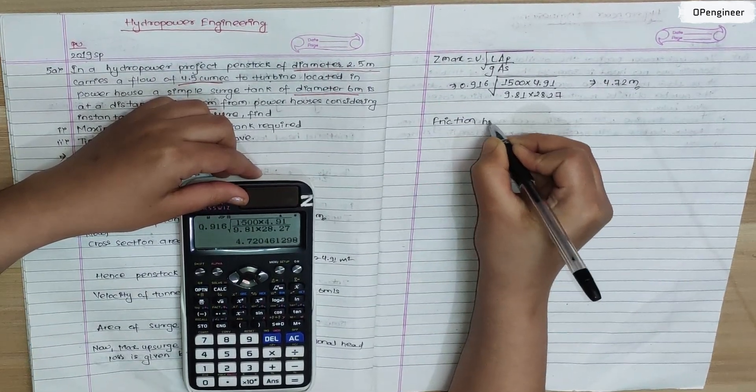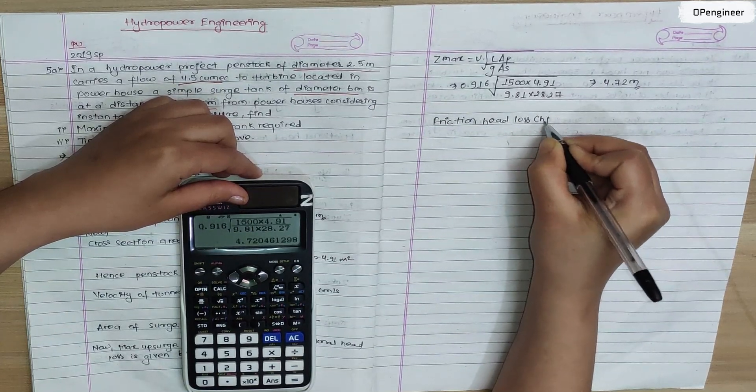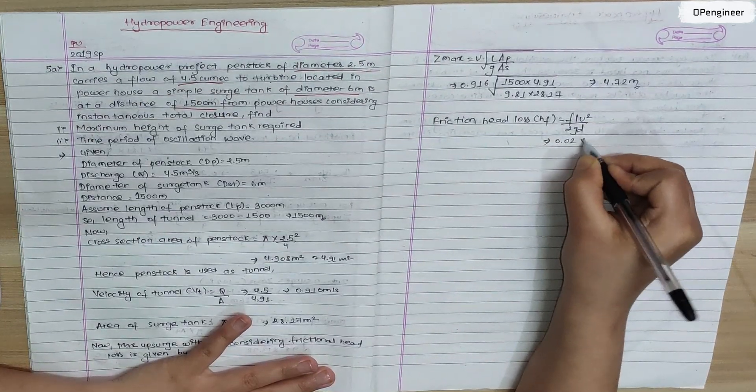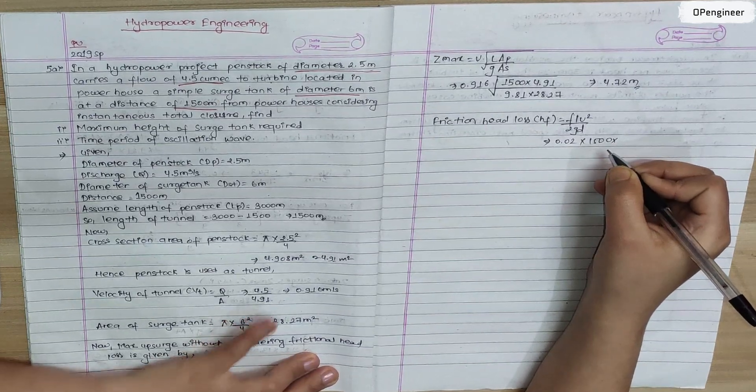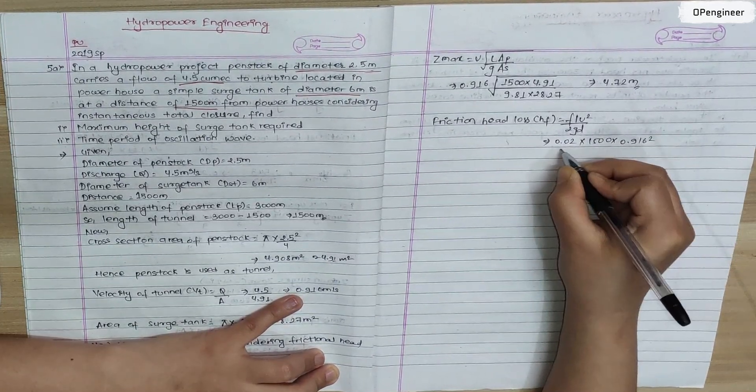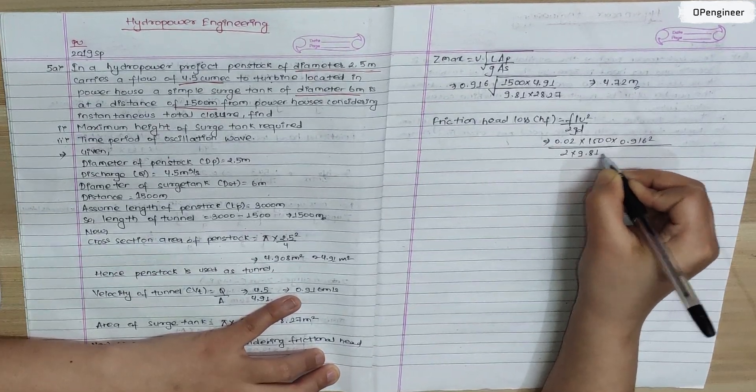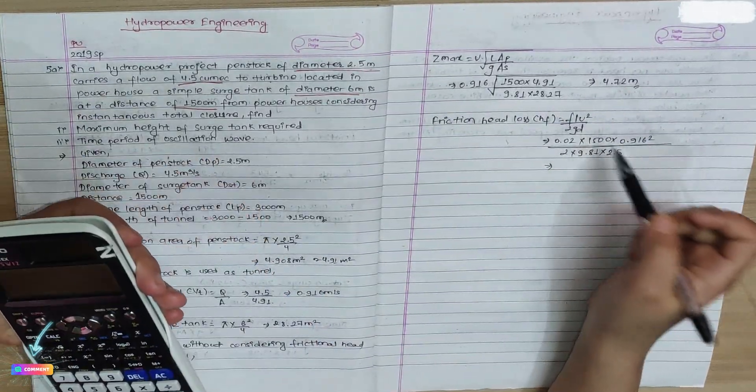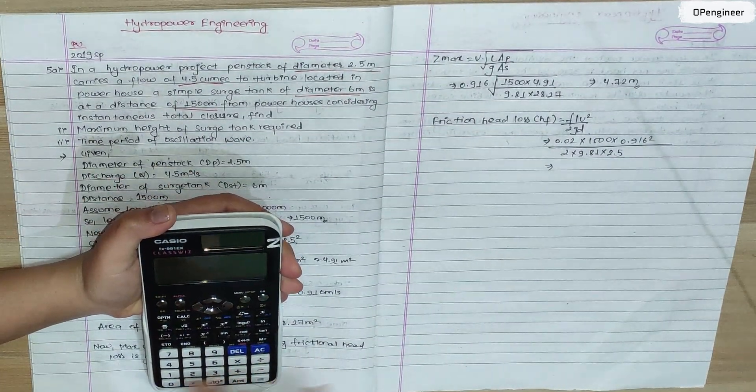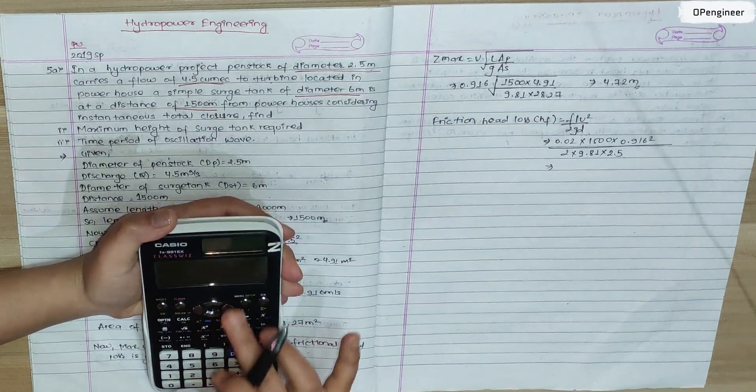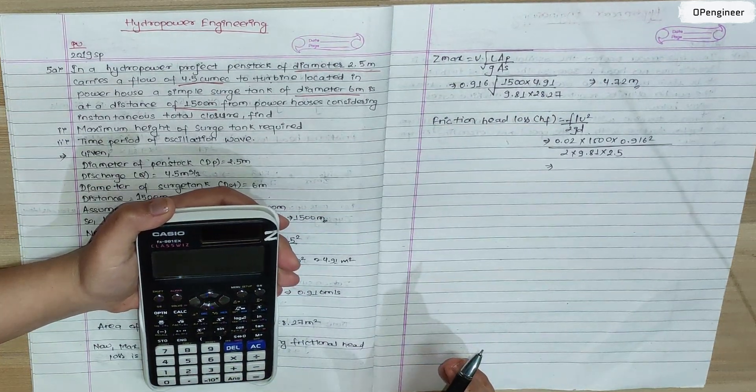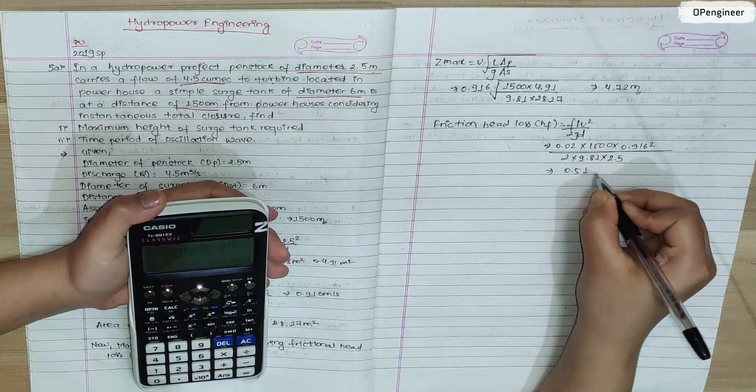This is friction head loss. Frictional head loss formula is F L V squared by 2 G D. F is 0.02 into length is 1500, V is 0.916 squared, 2 into 9.81 into 2.5. So length of tunnel and velocity of tunnel, diameter of tunnel. So now 0.02 into 1500 into 0.916 squared by 2 into 9.81 into 2.5. This is the friction head loss, loss is 0.51 meter.